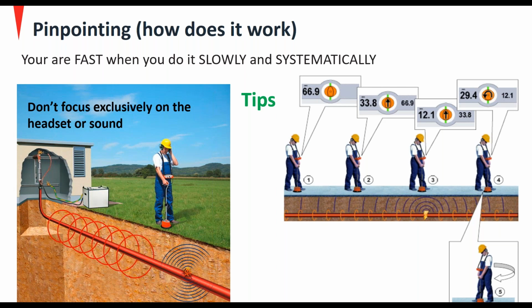Now, when you're going through this process, generally, if you were, say, at position 2 and you had the digiphone set to feet, that would indicate you're 33.8 feet away from the fault. When you see numbers roughly around 30 feet, that's where you're going to want to slow down a little bit and use the 2 or 3 thump rule, where now that you've got an indication that you're 30 feet from the fault, you probably want to let the thumper cycle 2 or 3 times and see if that 33 feet doesn't repeat. If it does, you know that it's picking up the fault sound and not some random noise.